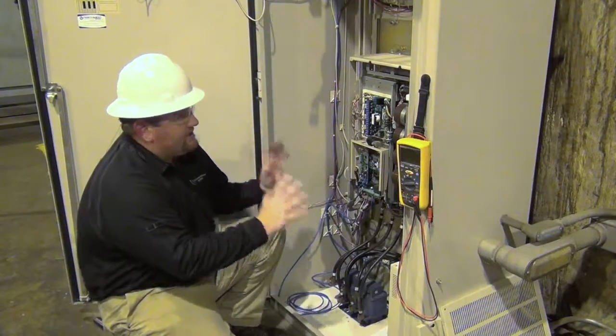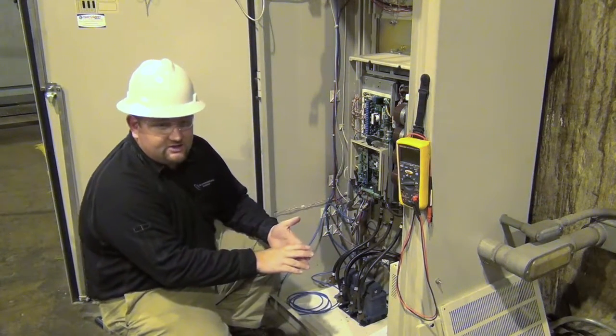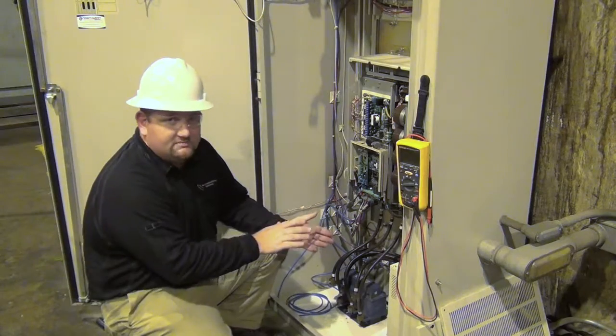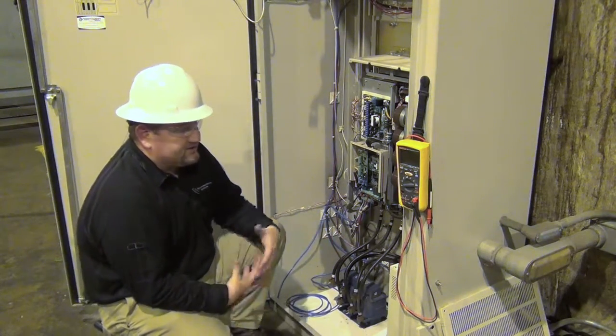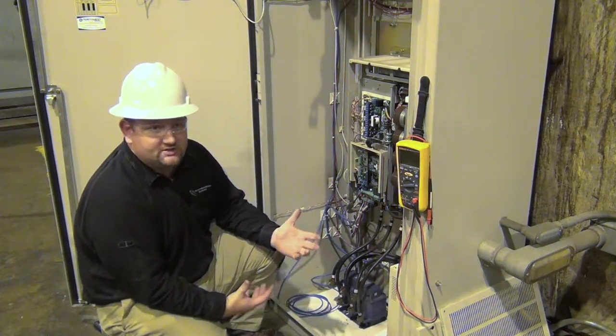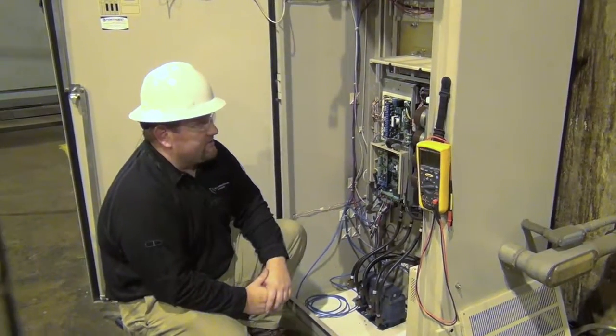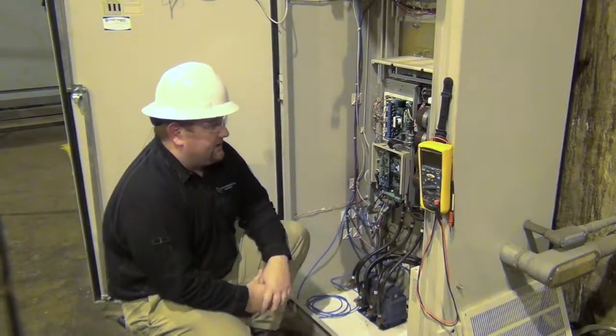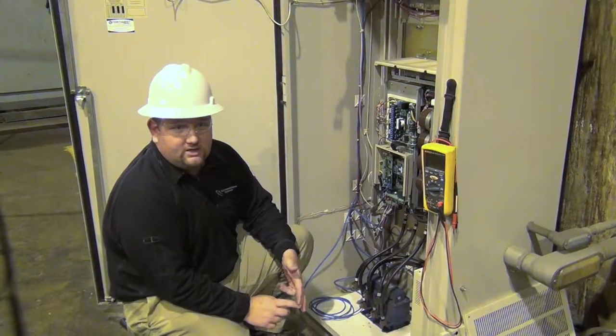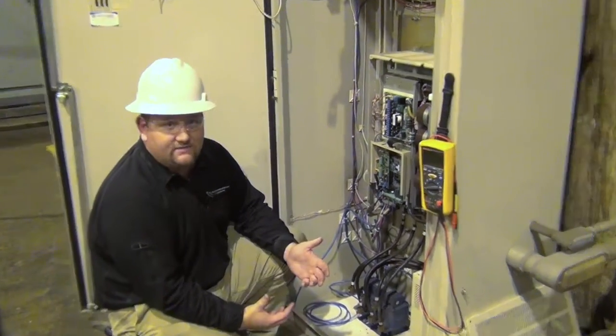So now what we're going to do, now that we've made our connections, we verified there's no loose connections, we visually inspected the drive, the next part is actually probably one of the most critical portions of doing the maintenance. Variable frequency drives are electronic equipment. The cleaner and the cooler we can keep them, the longer they're going to last for us.